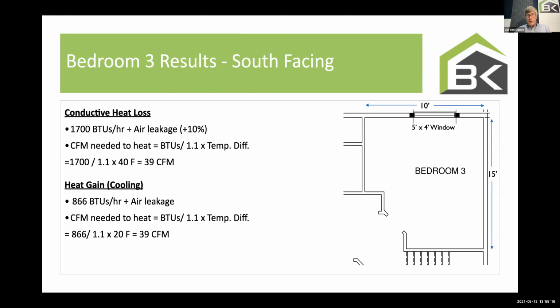Now, there are people on this call that are immediately going to raise their hand and go, well, wait a minute. The air coming off the top of the furnace was 40 degrees, but by the time I got out to bedroom number 3, what temperature was it? And here's the problem. Heat loss, heat gain programs don't give a lot of thought to that. They actually don't. You can put in factors that say I need more air, but you can start to imagine if I have a long run that went through unconditioned space. Oops, I'd want to consider that.